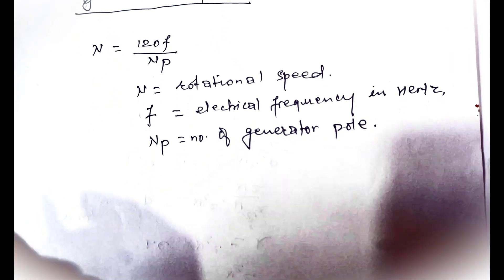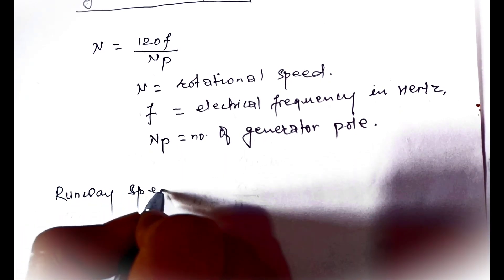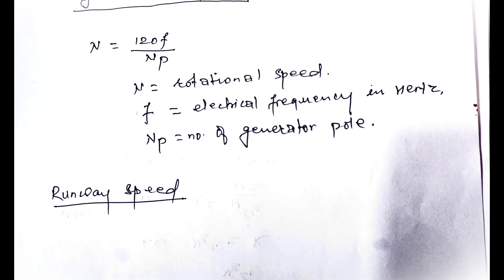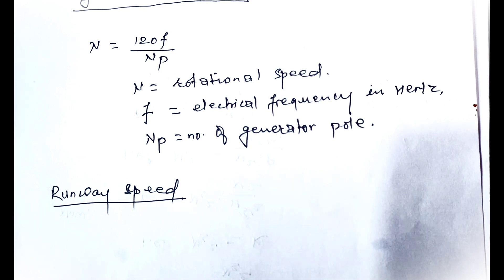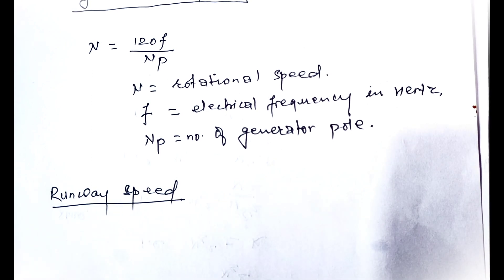Now let's discuss runaway speed. If the external load on the machine suddenly drops to zero and the governing mechanism fails at the same time, the turbine will tend to race up to the maximum possible speed, which is known as the runaway speed. The suggested runaway speeds for various turbine types for appropriate design and acceptable load variation are given in the following table.